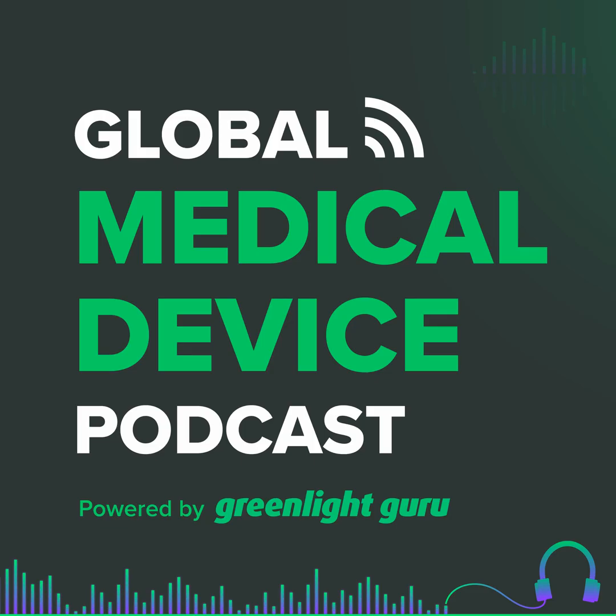So if you're planning on bringing this up in your pre-sub, and I've done it before, I would create a very distinct boundary, a line between the two, even so far as to say, for the first 30 minutes of the meeting, we're going to discuss the current device, and for the second 30 minutes or 15 minutes or whatever it is, we're going to discuss the potential modification via the PCCP. Otherwise you're going to get a tremendous amount of confusion as to, is this the current device? Is this the future device? The PCCP should be very specific to that particular device, not some class of devices.